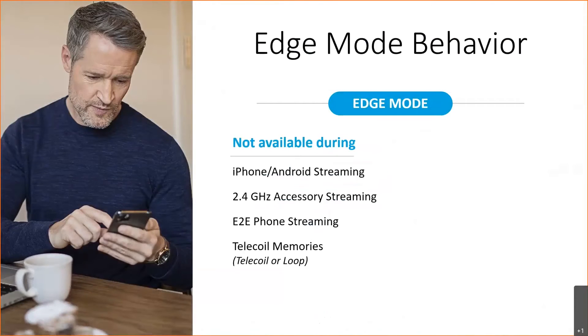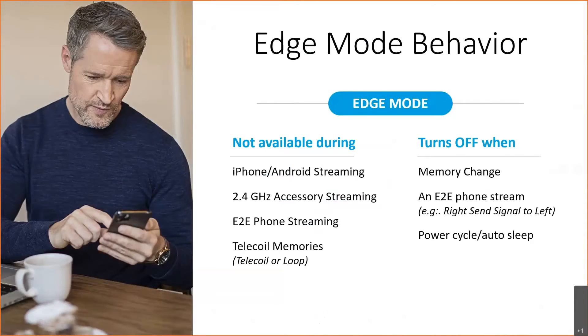Edge Mode is available in most situations. The only time it would be unavailable — and the patient would receive a communication indicator — is if they tried to engage Edge Mode while streaming from an iPhone, compatible Android phone, or one of the 2.4 gigahertz accessories. It also will not be an option during ear-to-ear phone streaming or when utilizing a telecoil. To disengage, they can use the same user control option used to engage it, change their memory, start ear-to-ear phone streaming, or power off the hearing aids.